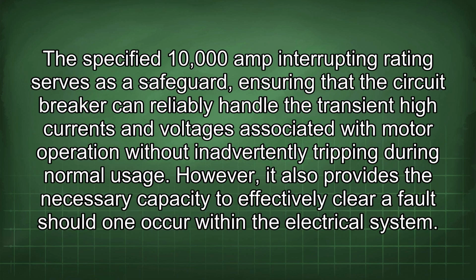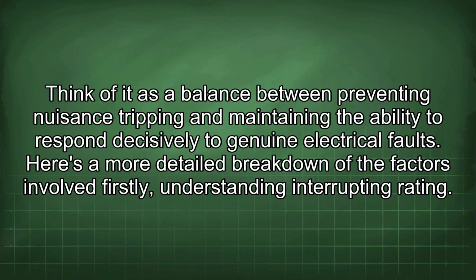The specified 10,000 amp interrupting rating serves as a safeguard, ensuring that the circuit breaker can reliably handle the transient high currents and voltages associated with motor operation without inadvertently tripping during normal usage. However, it also provides the necessary capacity to effectively clear a fault should one occur within the electrical system. Think of it as a balance between preventing nuisance tripping and maintaining the ability to respond decisively to genuine electrical faults. Here's a more detailed breakdown of the factors involved.